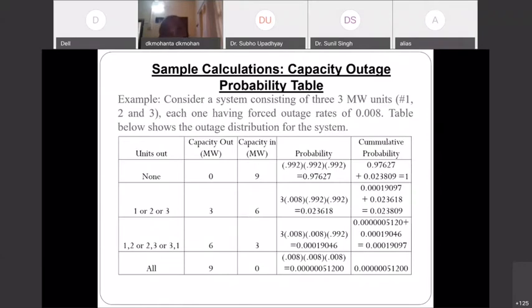What is the cumulative probability that loss of load will be more than 6 megawatt? It will include 6 megawatt outage as well as 9 megawatt outage. So this summation plus this summation is the cumulative probability of loss of load or outage or capacity greater than 6 megawatt. Now, 3 megawatt and above will include 3 megawatt, 6 megawatt, 9 megawatt. So the probability that capacity outage will be 3 megawatt or more will be this plus this plus this. And what is the probability of 0 megawatt or more? The cumulative probability will be 1. Because we will be using this for calculation of loss of load probability or loss of energy expectation.